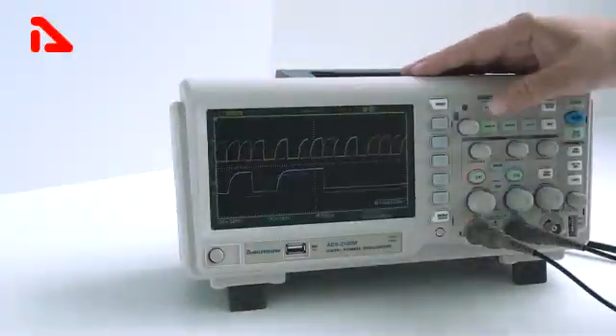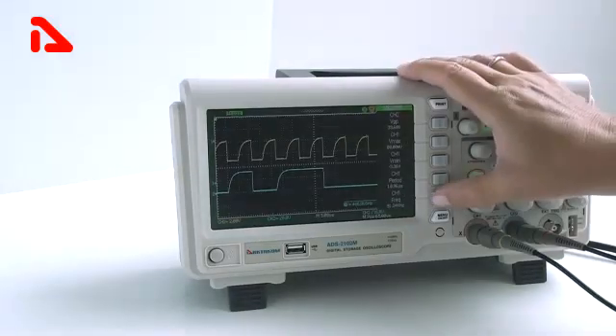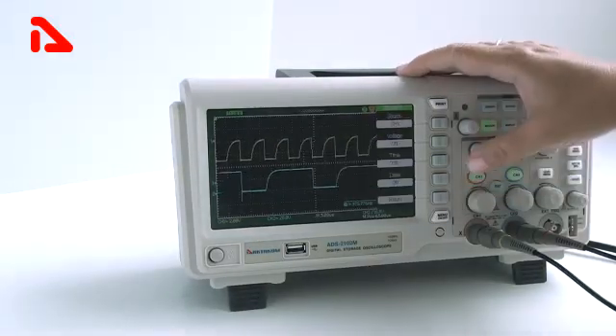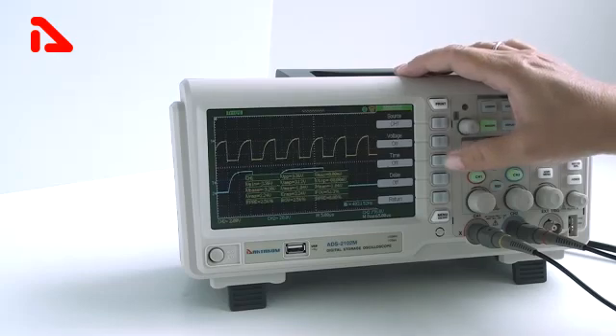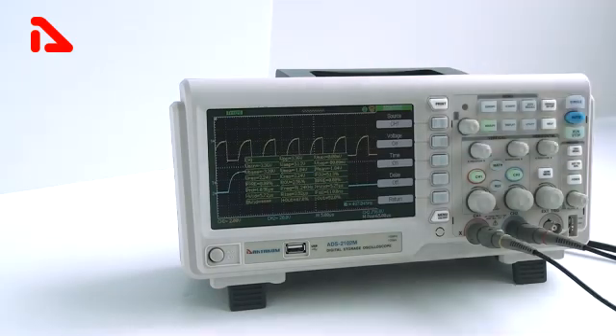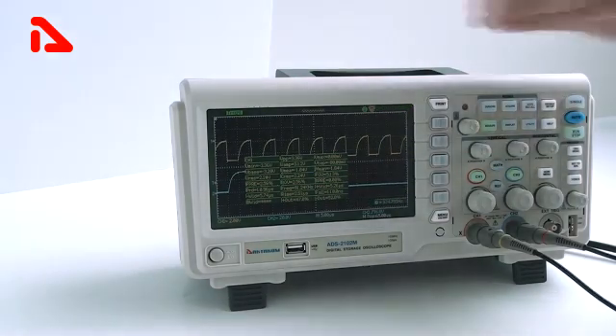One of the main advantages of this device is 32 automatic measurement functions per channel. By capturing the signal and activating the automatic measurement, you can immediately obtain all the parameters of measured signal, and the same for the second channel.